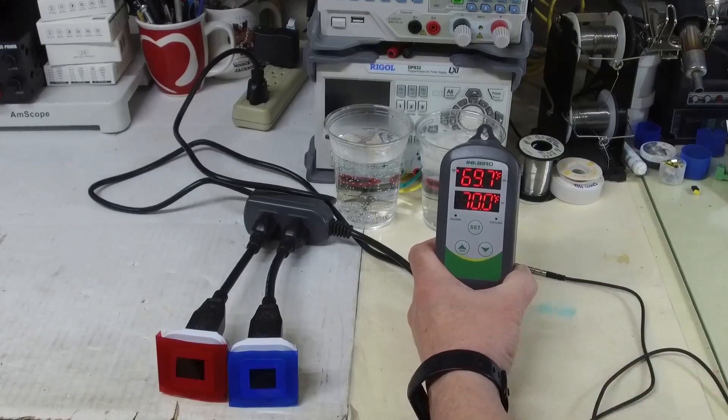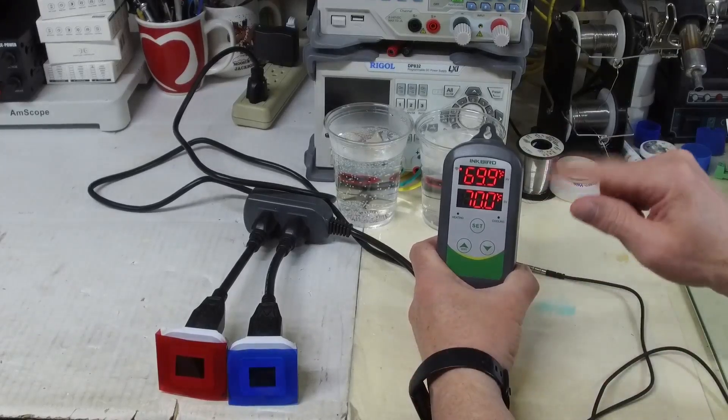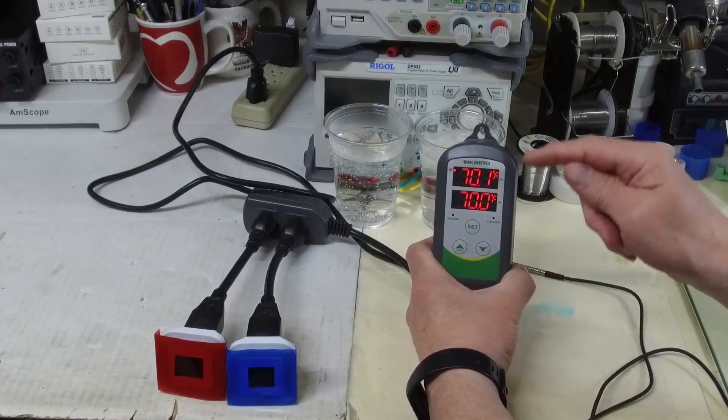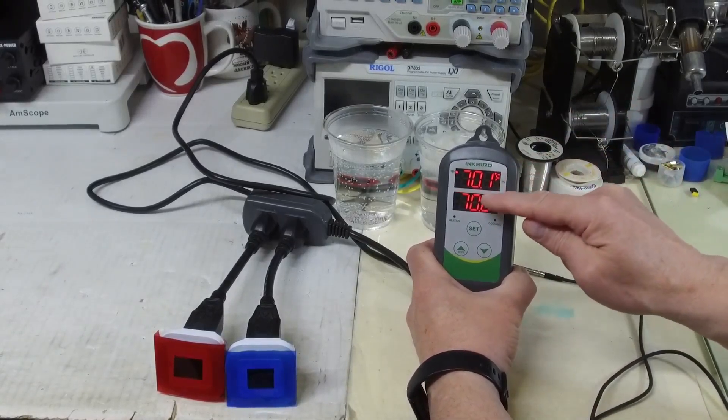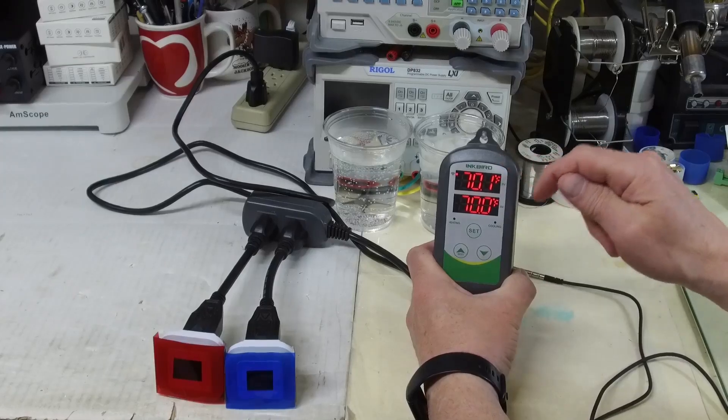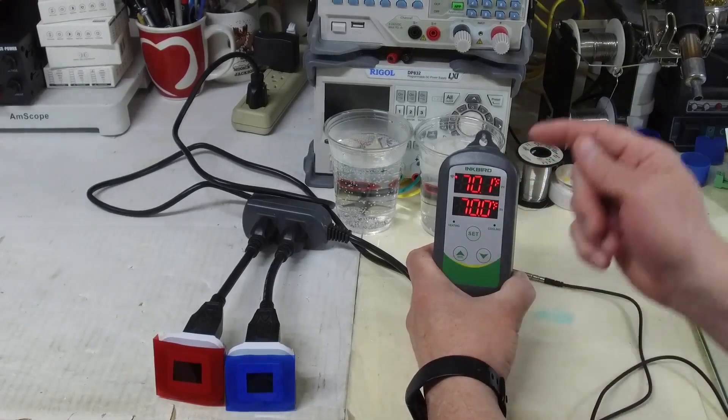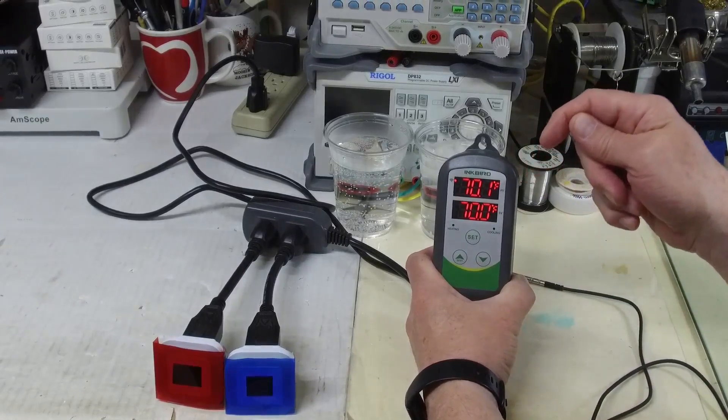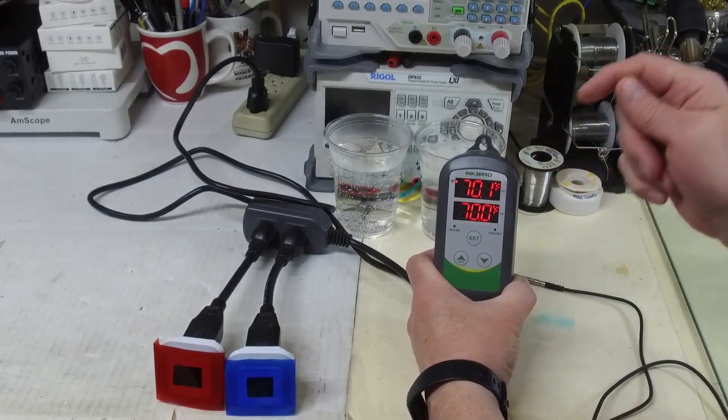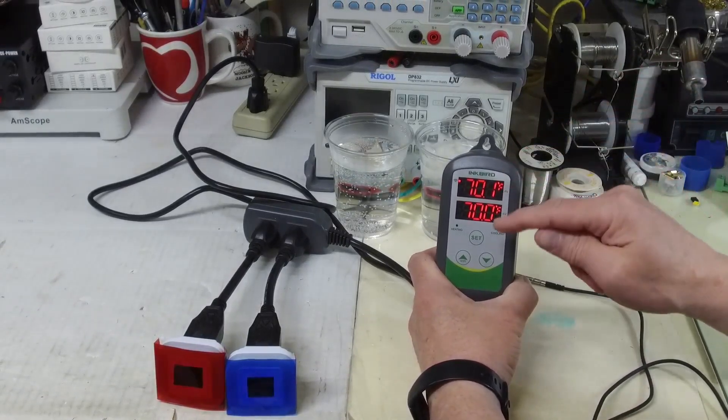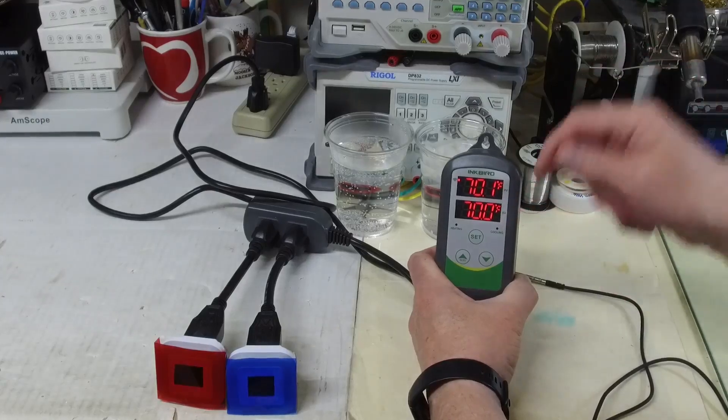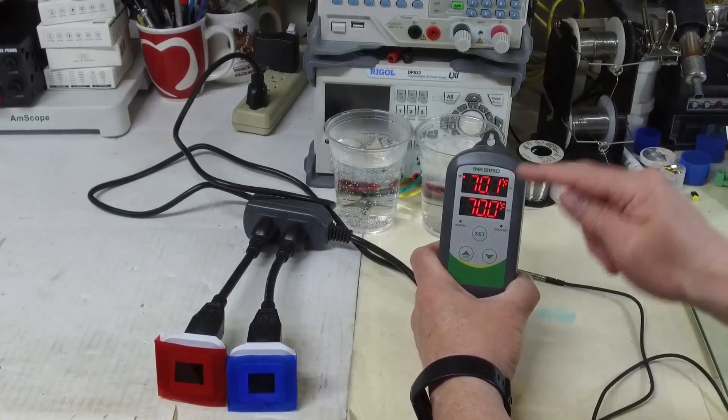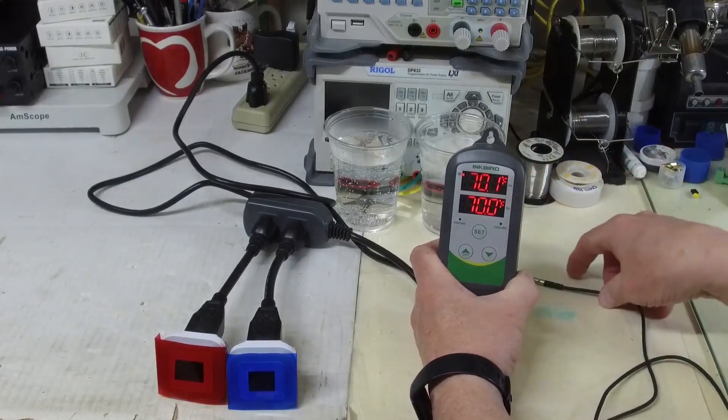But what happens when we exceed one of those set points? Initially I thought that if we got up to 80 degrees it would turn on the cooling and when it got back to 80 degrees the cooling would turn off, but that's not what it does. It will go all the way back down to 70, and I'll show that in a graph and I'll demonstrate that right now.